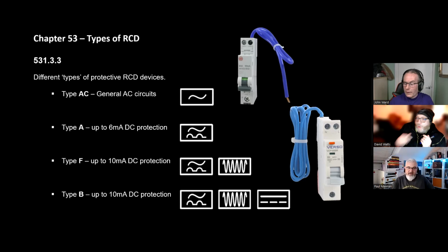And type B, for which the standard really needs to be rewritten, and it is because it's in draft actually, is also 10 milliamp, but it gives you all variants of DC, whether it be battery or switch mode power supply or pulsed or whatever type of chopped waveform you encounter. So my personal opinion is everything should be type B, but it's prohibitively expensive and the technology isn't miniaturized enough. So type A RCBOs with a type F maybe for your kitchen is my recommendation.